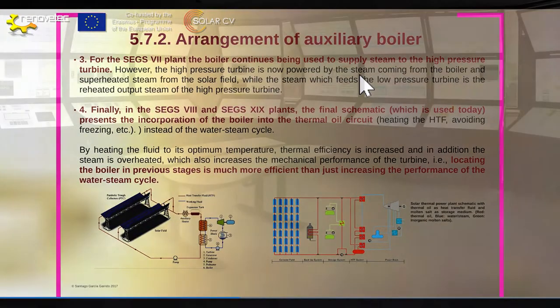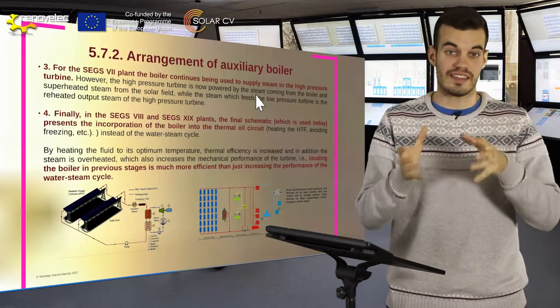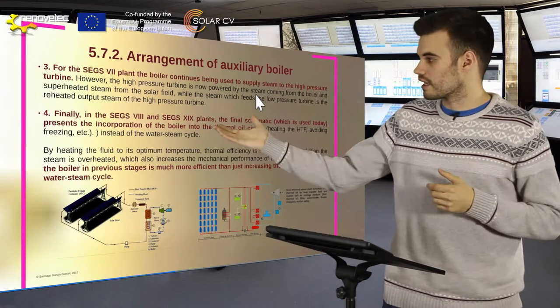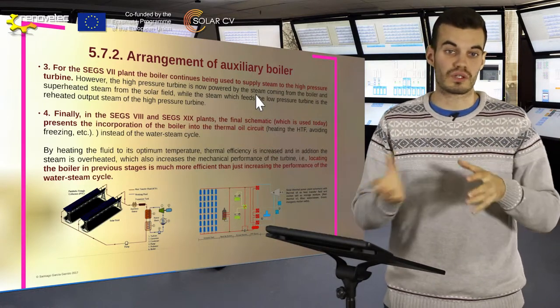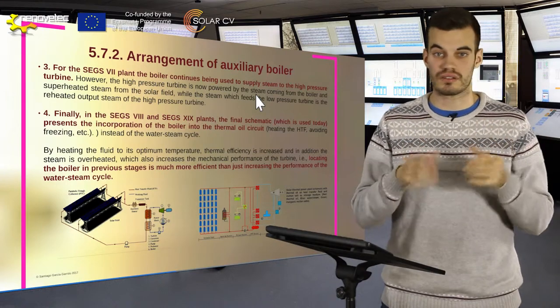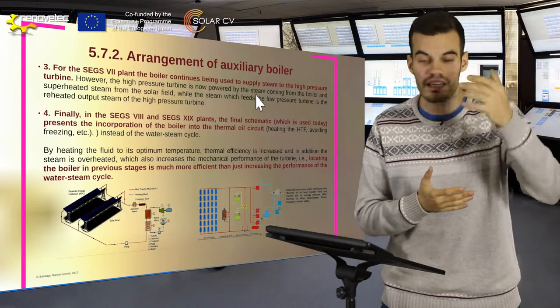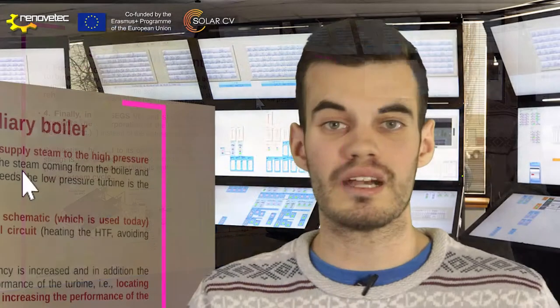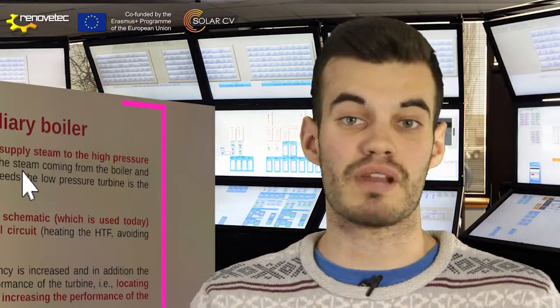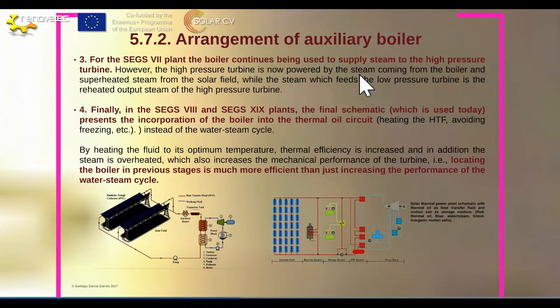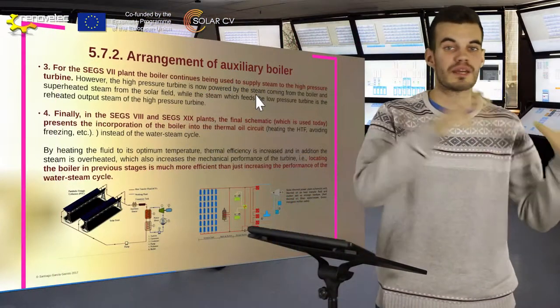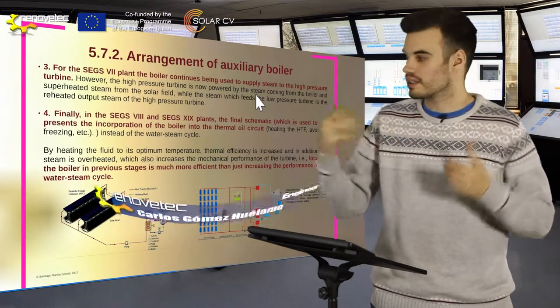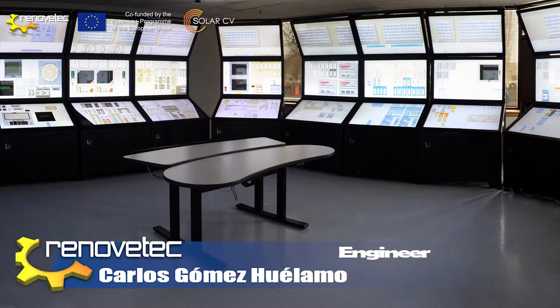Now we have a third possibility, and this is in the SEGS-7 plant. The auxiliary boiler was considered in the same position — that is, it supplies overheated steam to the high-pressure turbine. However, the low-pressure turbine is fed by the reheated steam from the output of the high-pressure turbine. So the final position of the auxiliary boiler is going to be considered in SEGS-8, 9, and 10 plants.